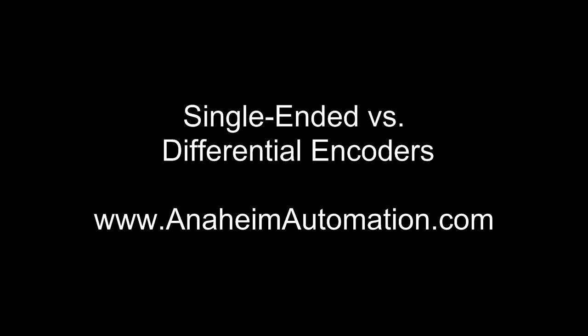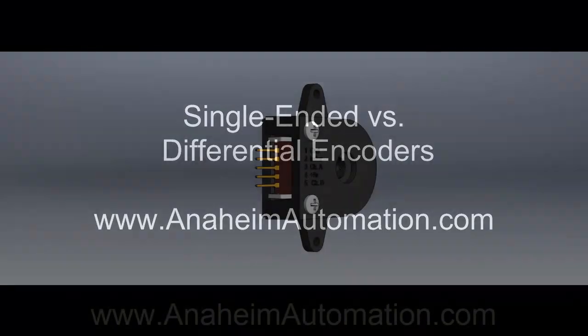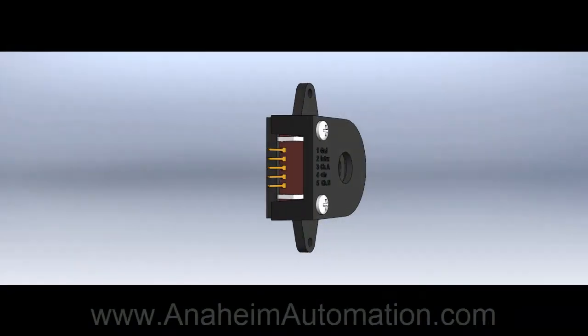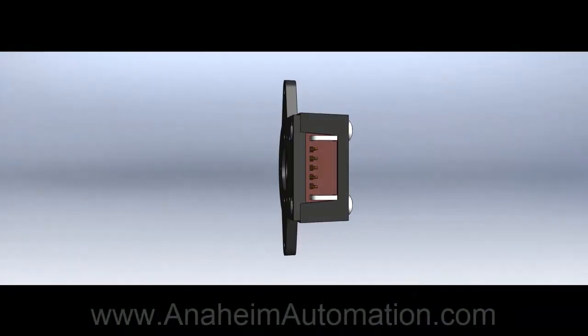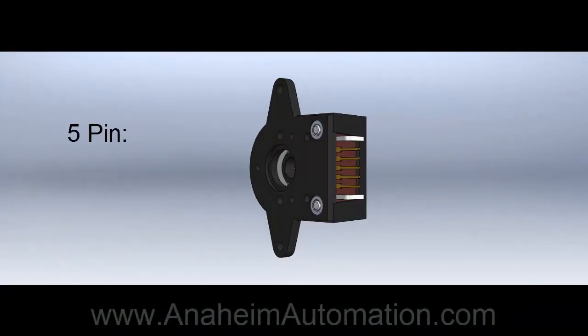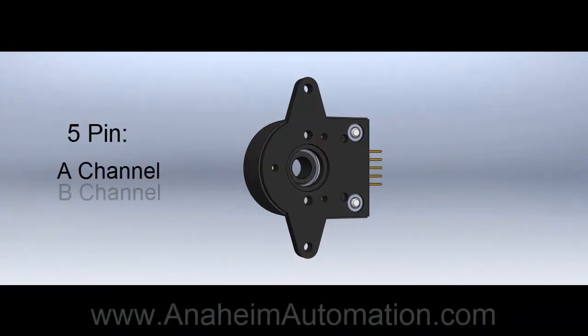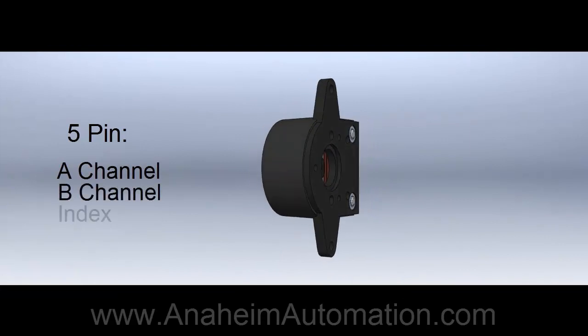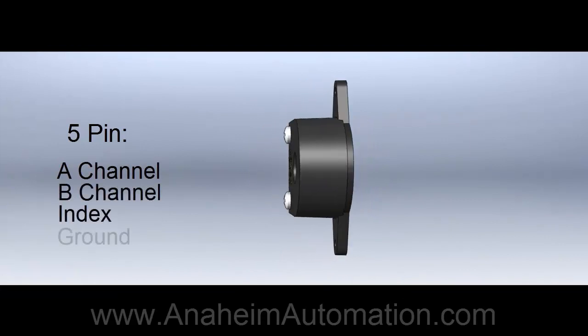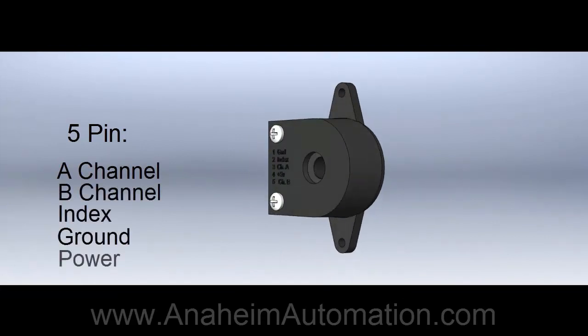This video will be discussing the difference between single-ended and differential-type encoders. Single-ended encoders come in a 5-pin standard consisting of an A-channel, B-channel, index channel, ground, and power inputs.